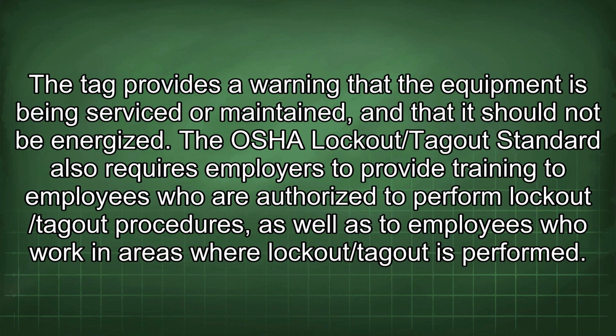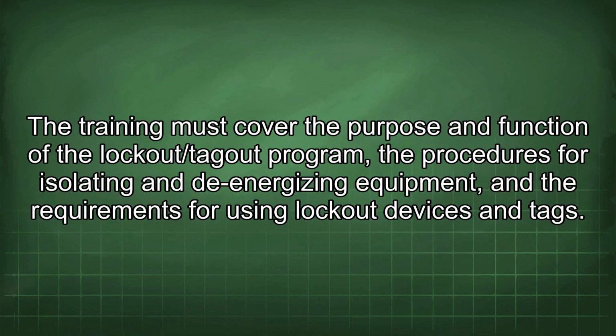The OSHA lockout/tagout standard also requires employers to provide training to employees who are authorized to perform lockout/tagout procedures, as well as to employees who work in areas where lockout/tagout is performed. The training must cover the purpose and function of the lockout/tagout program, the procedures for isolating and de-energizing equipment, and the requirements for using lockout devices and tags.